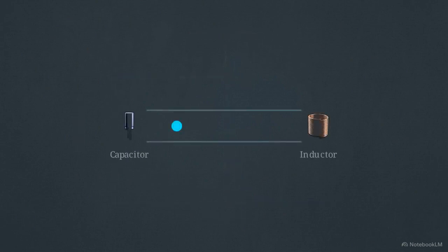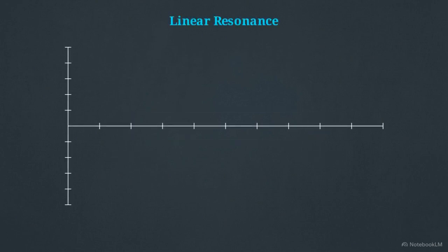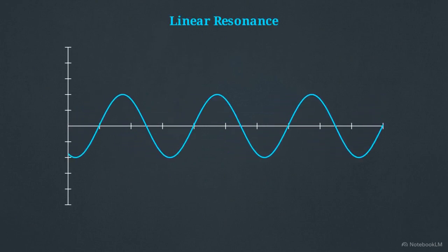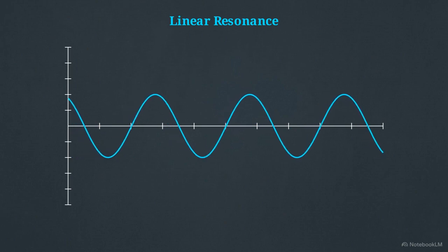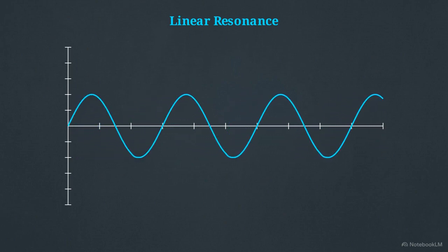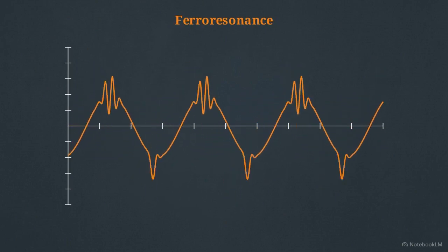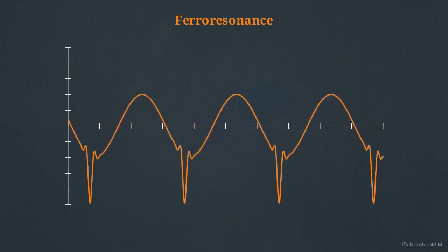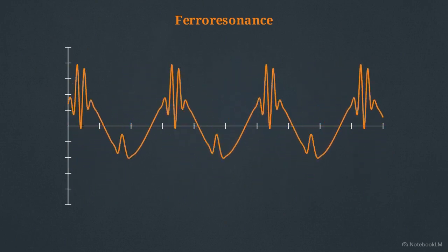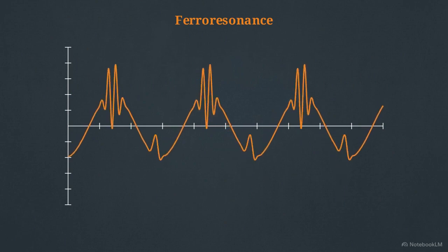Because the transformer's inductance is no longer a fixed number, the smooth energy exchange shifts. The circuit enters a state where the voltage and current are no longer governed by a stable, linear balance. A standard linear resonance behaves like a tuning fork. It rings at one clean frequency. Ferroresonance produces temporary overvoltages, characterized by erratic jumps across multiple frequencies, creating a distorted wave.